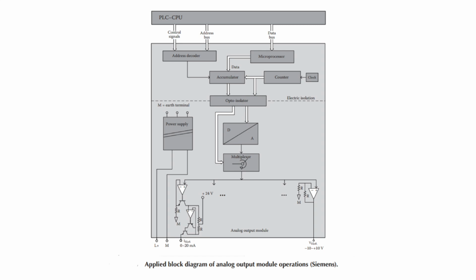The digital and the analog circuits in the module are electrically isolated using an optical isolator. This optical isolator is used mainly to isolate and to ensure the safety of the system. The analog output modules often require an external power supply with specific voltage and current requirements. The typical analog devices controlled by these modules include small motors, servo valves, DC servo motors and drivers for high power motors with varying speeds.